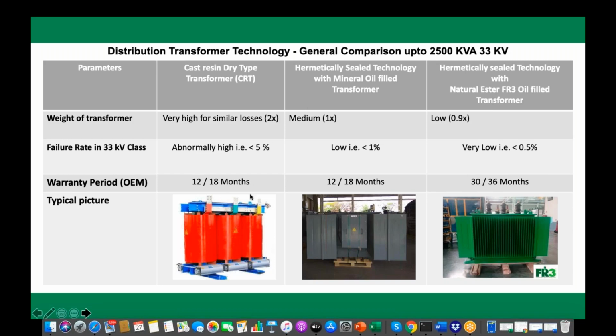And when it fails, the repairability is havoc, because a dry type transformer you cannot repair, especially a cast resin transformer. You have to throw away the coil and put a new coil, but you can replace the coil. When it comes to a liquid filled transformer, both mineral oil and natural ester, you can repair as much as needed. Although we say we should have fit and forget, there are still failures, and repairability is a need of the country, because we cannot afford to invest again in new equipment looking at today's economy. So when you see transformers from a utility point of view, a lot of utilities have their own repair center if they don't have a contractor, and for them it becomes too easy to maintain and repair liquid filled transformers as against dry type transformers.